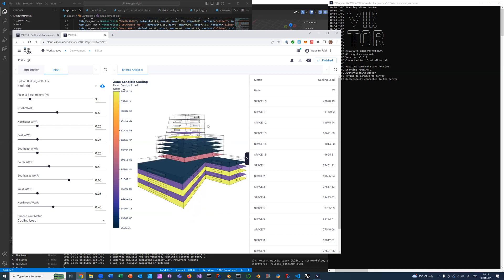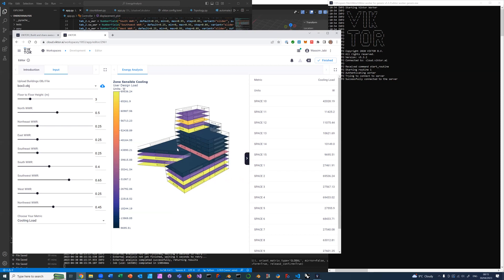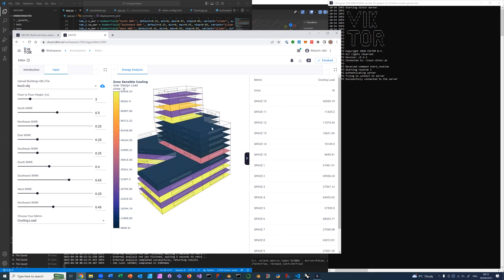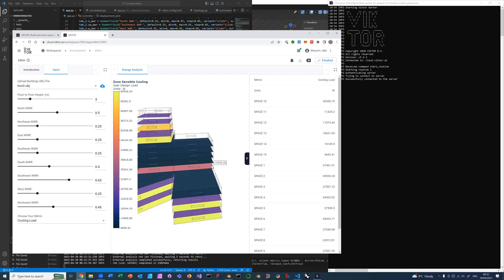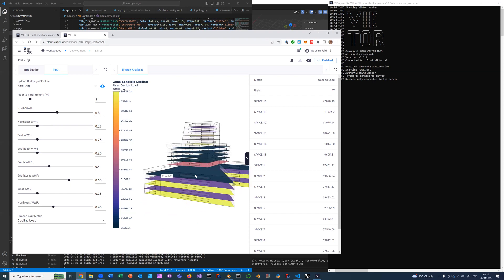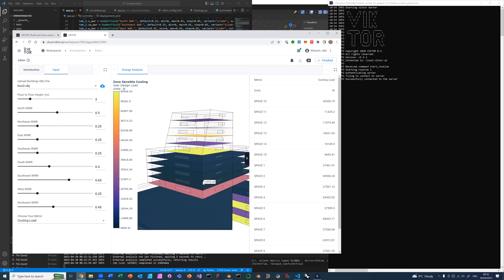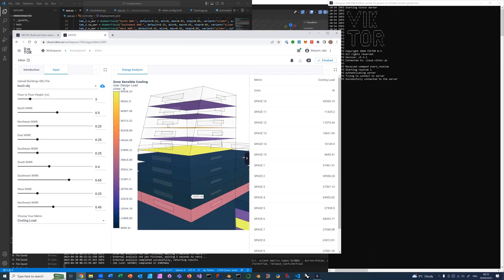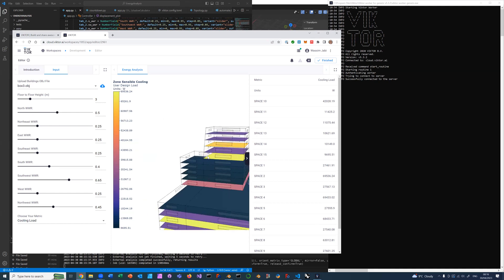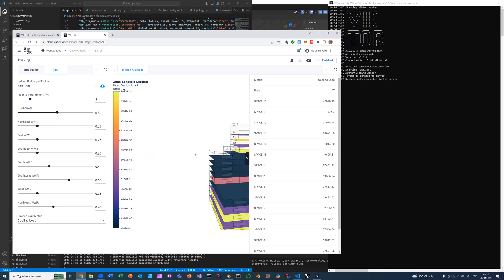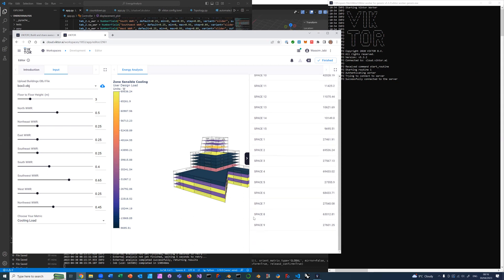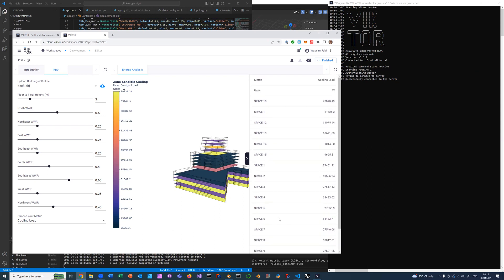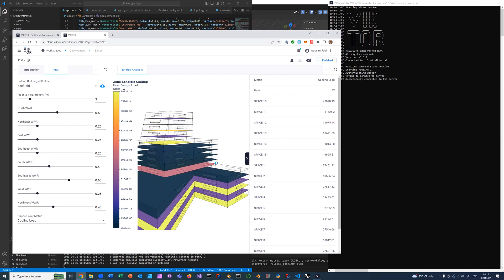North is that way, so you can see here, for example, north windows are larger because we've said that the north windows have a 0.5 window-to-wall ratio, as well as the south and the southwest are a bit larger. You'll notice that even the inclined walls are treated correctly and they get the correct windows on them. The colors on the floor you can match against the scale. They are listed here in terms of the cooling load and the wattage.